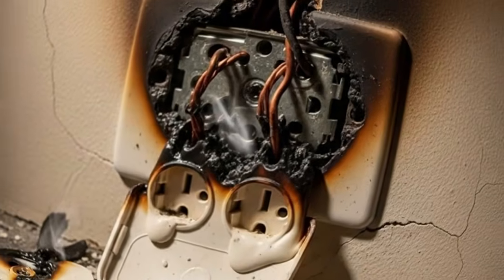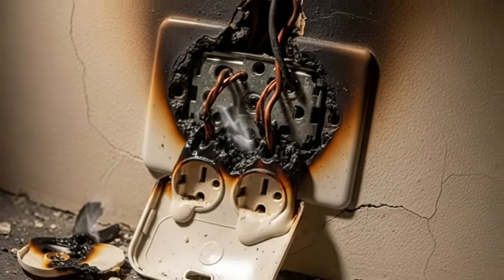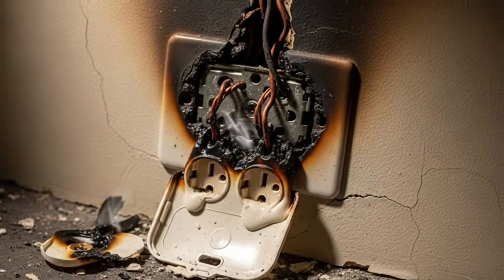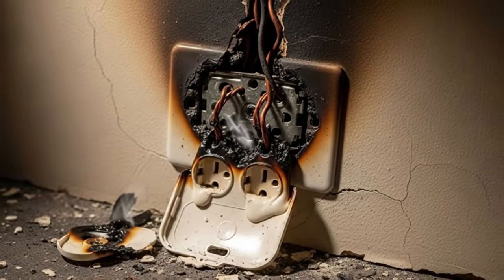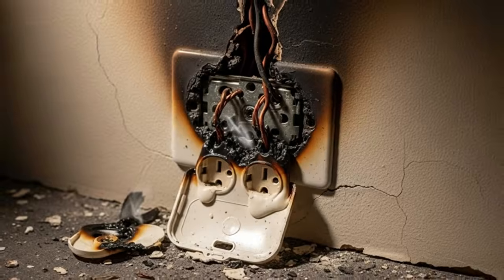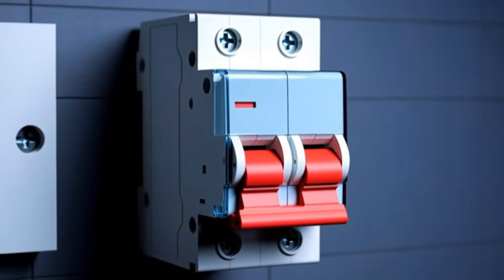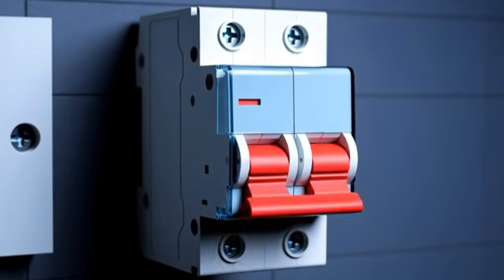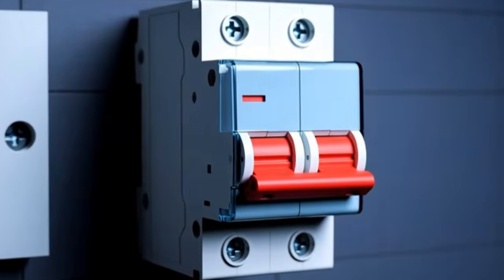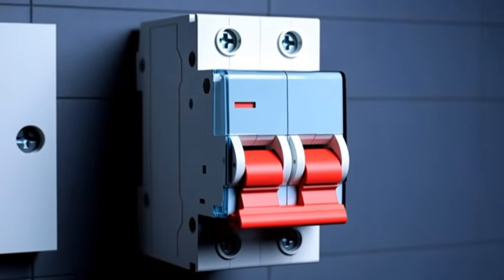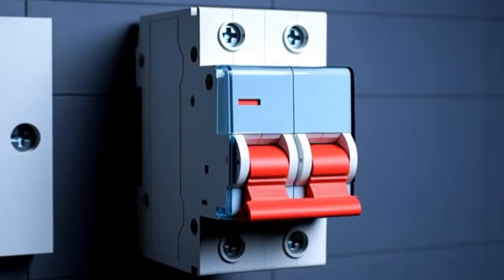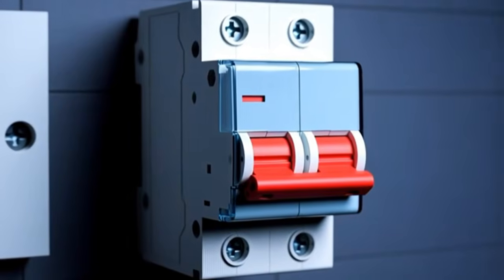Heat, age, physical damage, rodent chewing, and improper installation can all cause insulation to fail and allow wires to contact each other. If your breaker trips immediately, the instant you flip it, not after a few seconds, but instantly, a short circuit is the most likely cause. You'll need to identify where the short exists before the breaker can be safely reset.